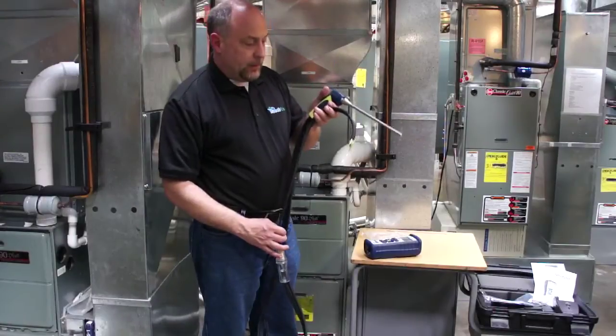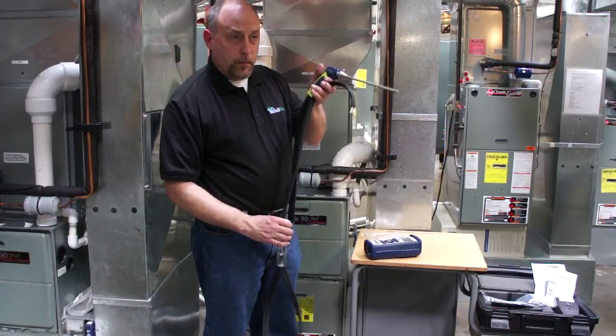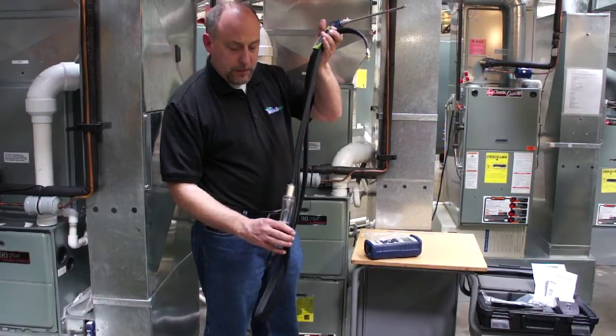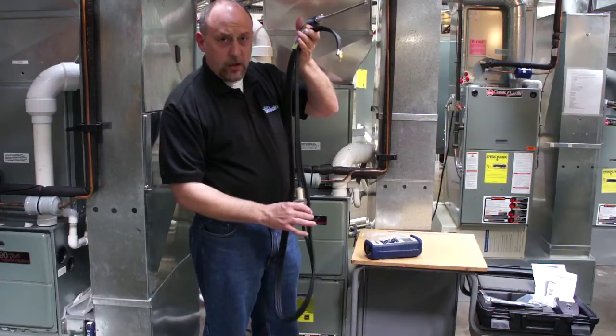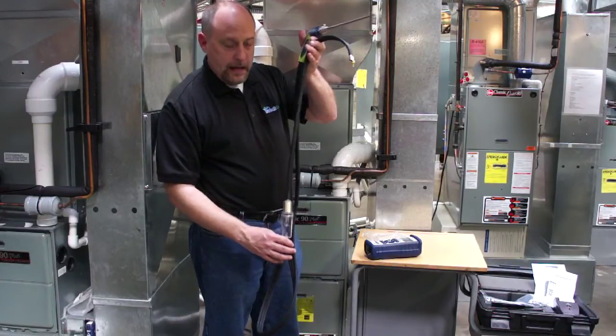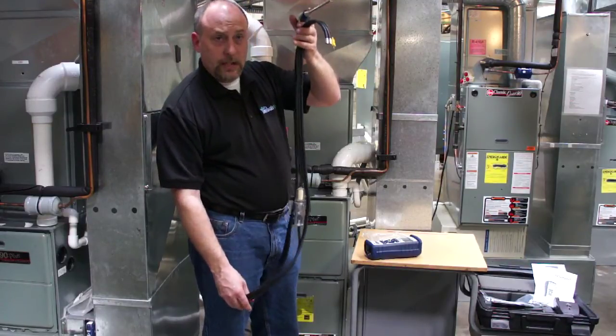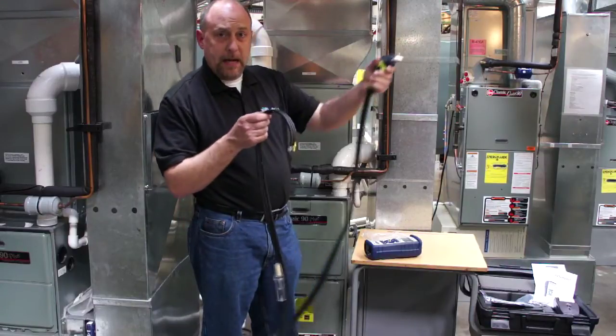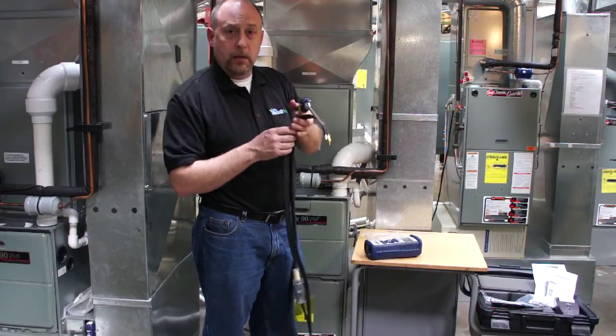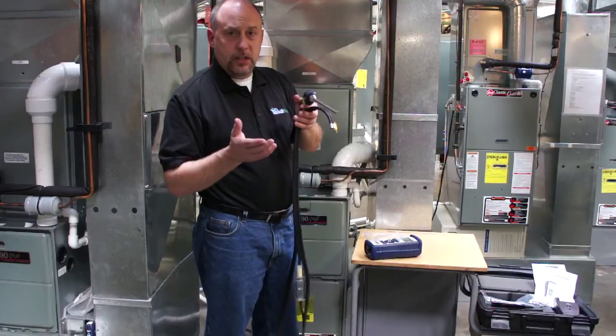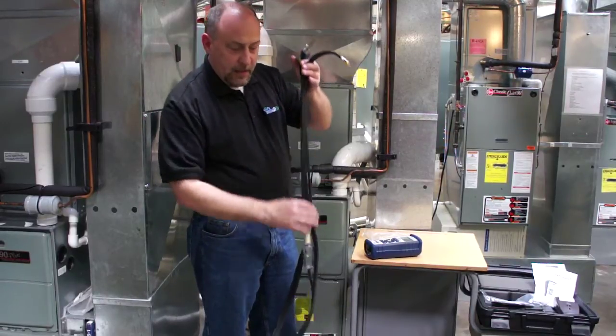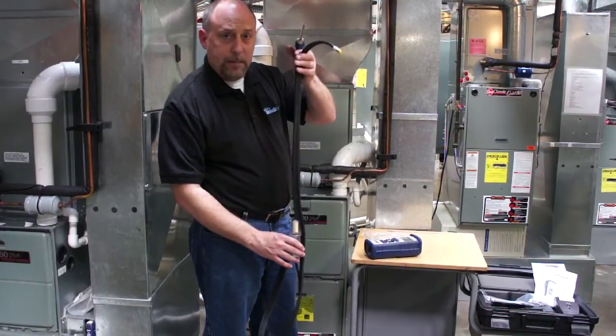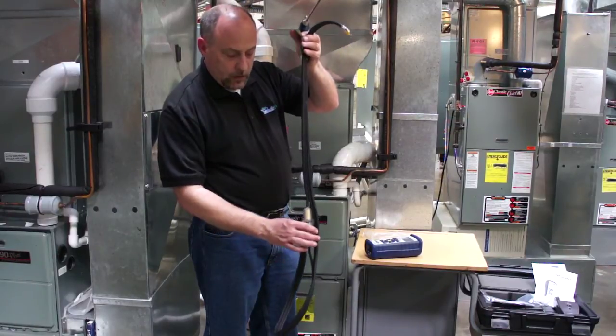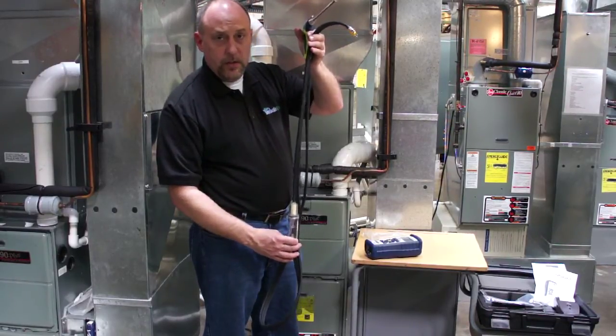The probe assembly for the INSIGHT is pretty similar to all the other Bacharach probe assemblies you might have seen. Again, it's got the water trap integrated into the hose set, and they give you a really nice long hose set for a couple reasons. Number one, so you can get back behind a burner or back behind a boiler if you're doing your air adjustments in the front. But the other thing is we need to make sure that this water trap hangs straight up and down so that we don't get any moisture into the O2 cells of the instrument.